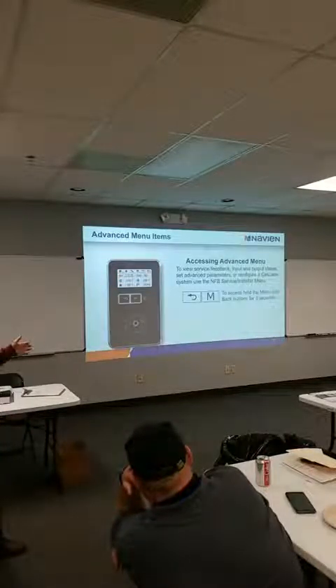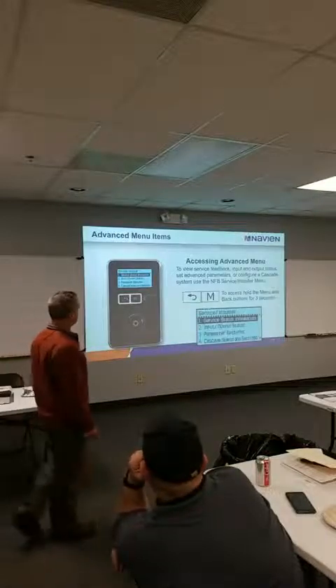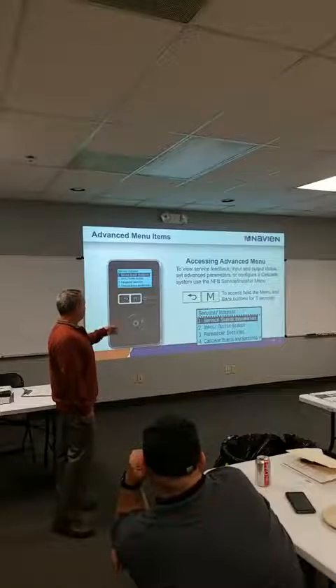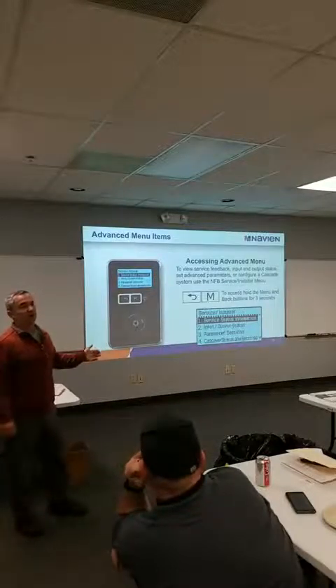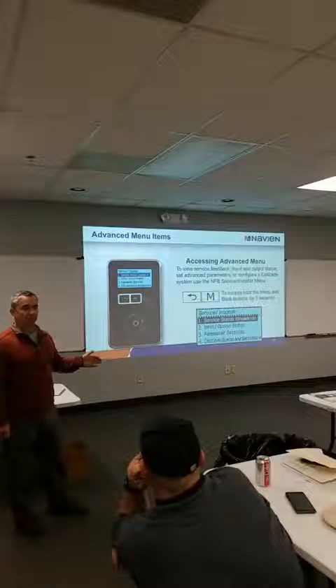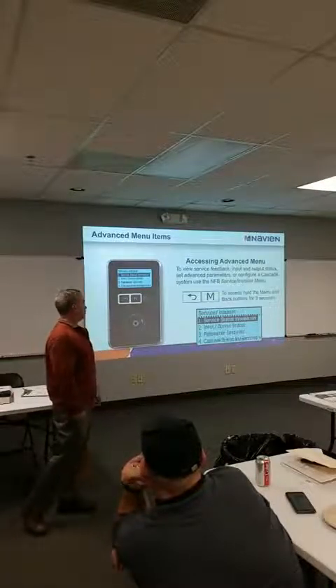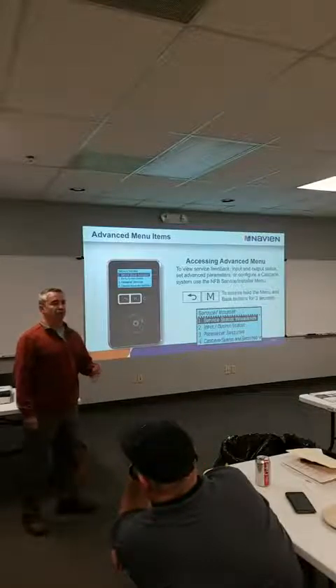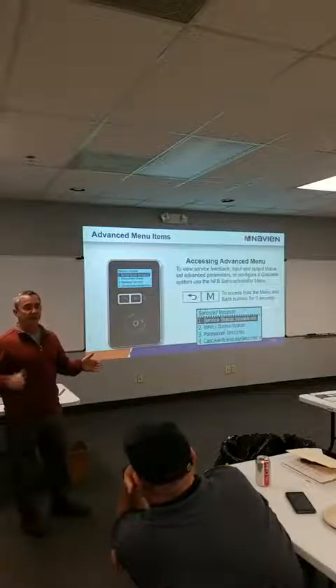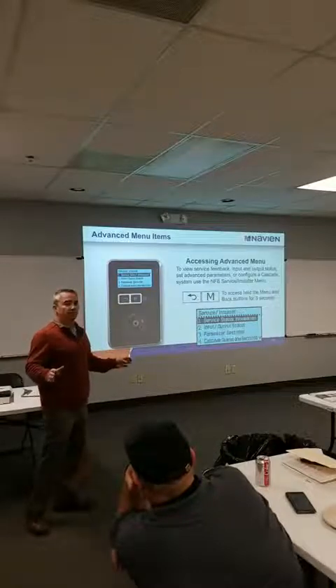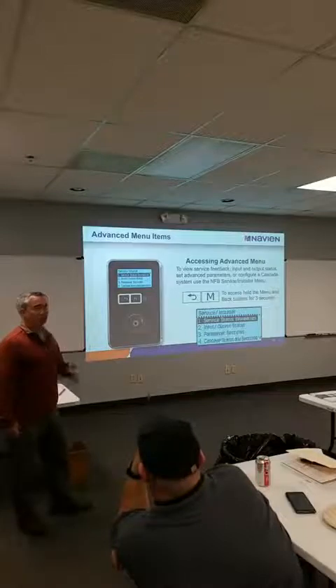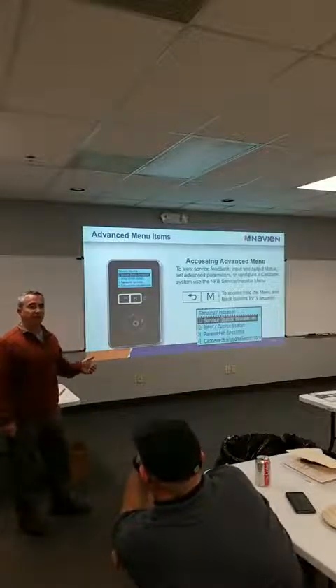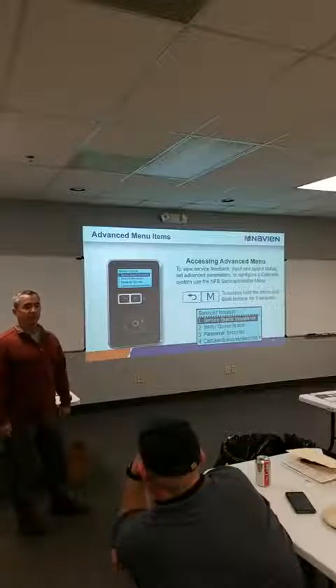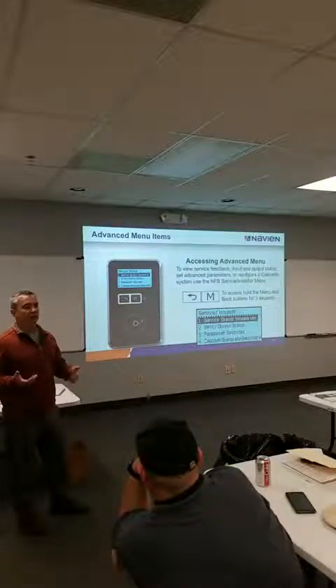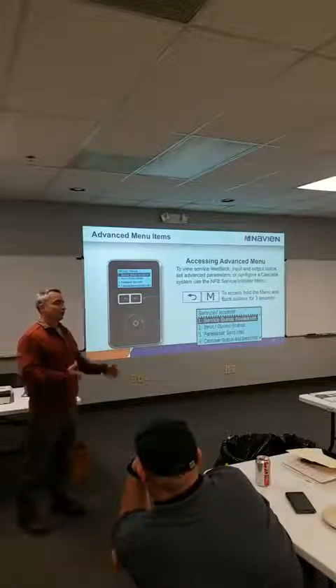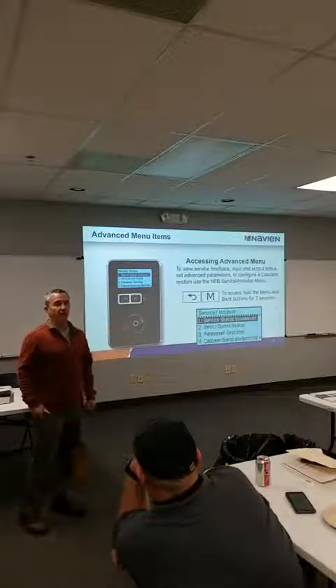We also have an advanced installer menu. If you hold down those two side buttons, return and menu, it puts you in our advanced menu. That allows you to change any parameter that we have available in the system. You can set up your cascade mode there. If you want to put boost control on, you could change the default timer. All your defaults, to any possible coding that we have, you can go in and change right there. Not that you ever need to do that, but that's where we would make adjustments if we had to. Sometimes you want to tweak our default, or you want to run both pumps at the same time, or whatever. That's where you make your adjustments.